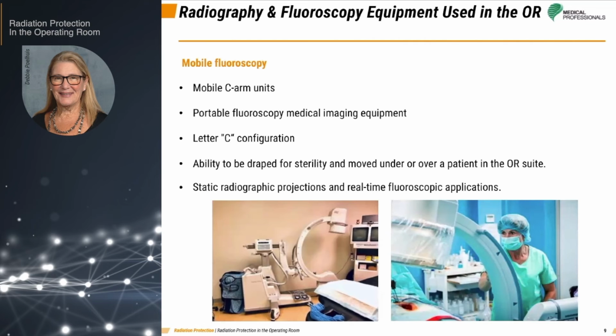And last but not least comes mobile fluoroscopy equipment, such as a C-arm. Portable fluoroscopy imaging is possible in the operating room thanks to mobile C-arm units. Because of their curved arm in the shape of a letter C, they are named such. On the upper arm of the C is the X-ray tube, and on the lower arm, the image intensifier. These C-arms can be used for static radiography studies as well as fluoroscopy studies.